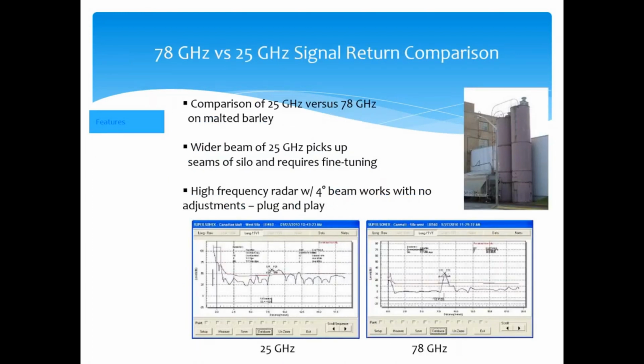This is an additional slide I put in that shows an echo profile between a 25 gigahertz radar and a 78 gigahertz radar in a solid silo. On the medium frequency 25 gigahertz, we've got a lot of noise, a lot of reflections coming off of different things inside that vessel. This is our true solids level, but there are multiple spikes before and after it, and at some point the instrument could pick up on one of those even though it's not true level. Whereas with our 78 gigahertz, we don't have any of those additional reflections coming back, and our true level is a nice clean spike, significantly higher than the threshold. This just goes to show you how much easier it is when you have that narrow beam in an application like this.